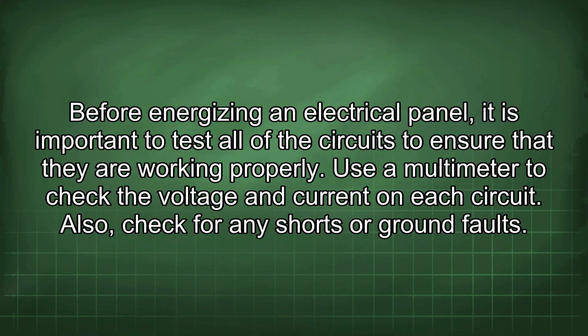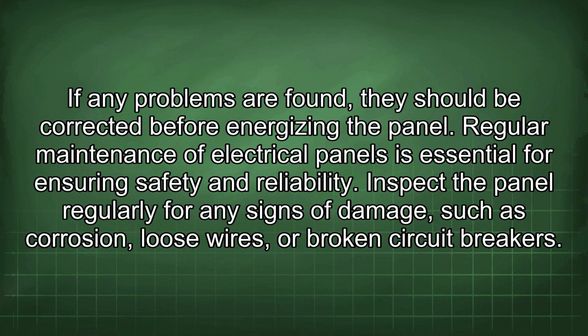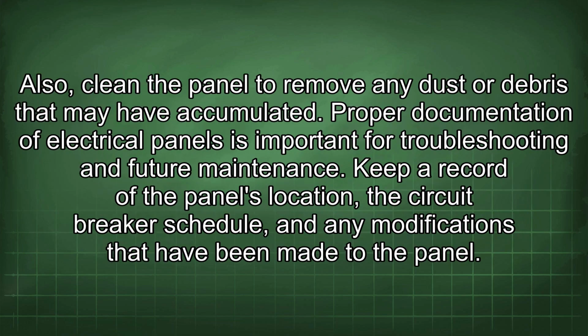Before energizing an electrical panel, it is important to test all of the circuits to ensure that they are working properly. Use a multimeter to check the voltage and current on each circuit. Also, check for any shorts or ground faults. If any problems are found, they should be corrected before energizing the panel. Regular maintenance of electrical panels is essential for ensuring safety and reliability. Inspect the panel regularly for any signs of damage, such as corrosion, loose wires, or broken circuit breakers. Also, clean the panel to remove any dust or debris that may have accumulated.